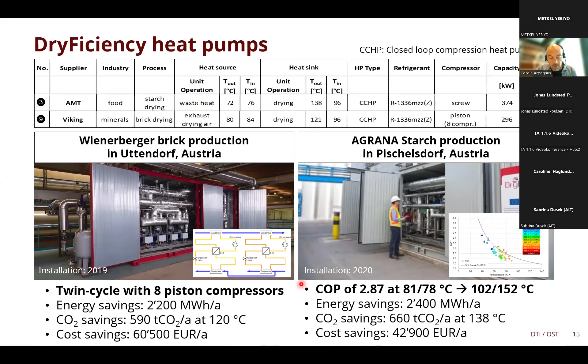So there are substantial energy and CO2 savings possible. These two examples show it quite nicely. Also, cost savings are stated here, 60,000 euros per year and 43,000 per year, so that the payback times can be cost effective. The COPs fit with other experimental data from other industrial heat pumps. So what are the learnings here? They learned about material compatibility, so the lubricant, refrigerant, and sealing materials. They also learned about the mechanical design, about vibrations, about integration into existing infrastructure, and process control was also one of the learnings, for startup procedures and data control measurement devices.